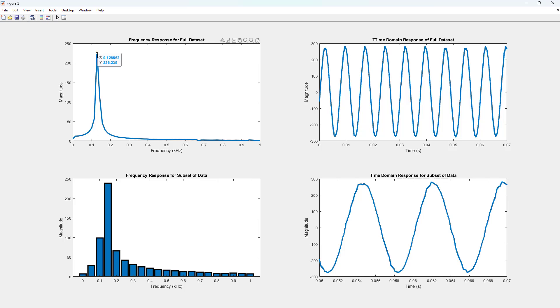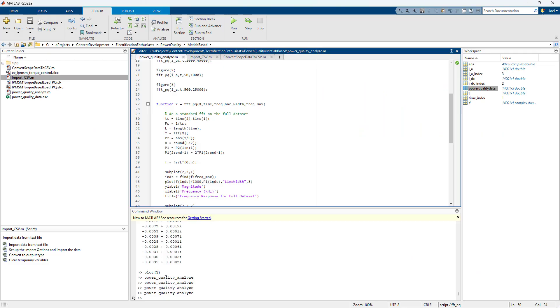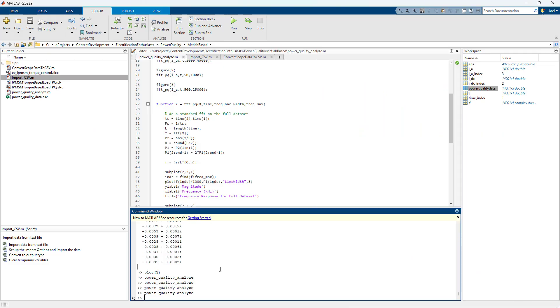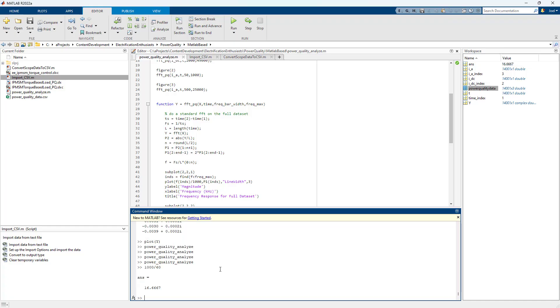Can I click there? That X is 0.128. Now this is in kilohertz. So that's 128 hertz. Why is there a peak around 128 hertz? Well, we're at 1,000 RPM. So 1,000 RPM divided by 60 gives me 16.6 hertz. But it's an eight pole machine. So my electrical frequency should be 8 that. So 133.